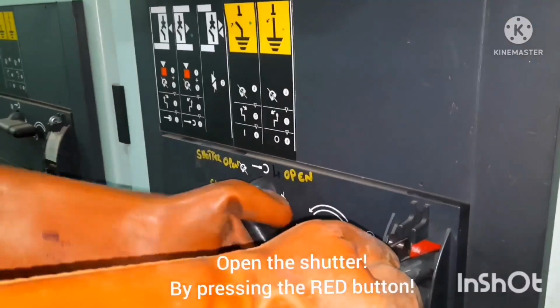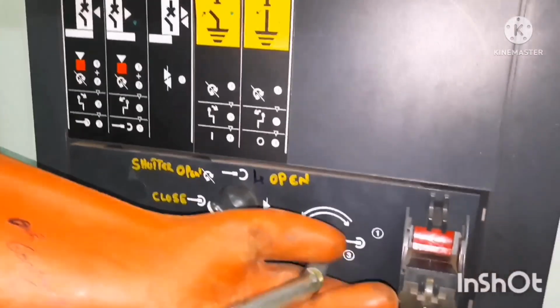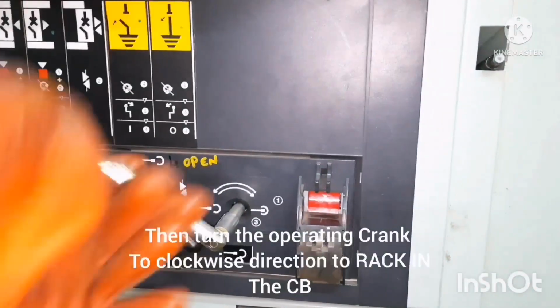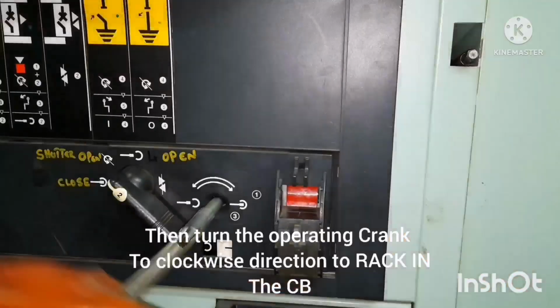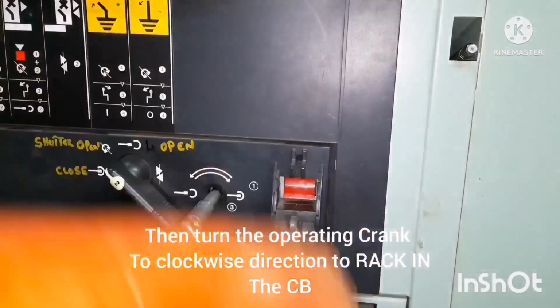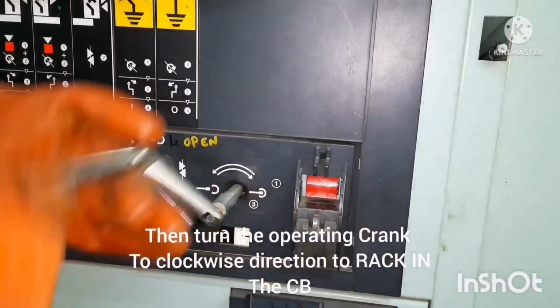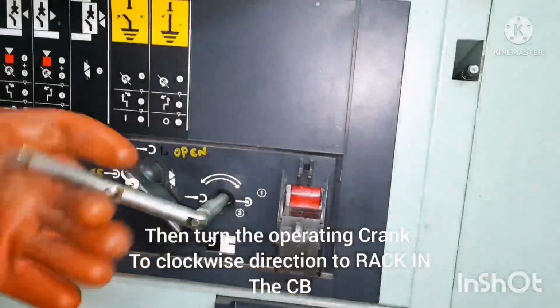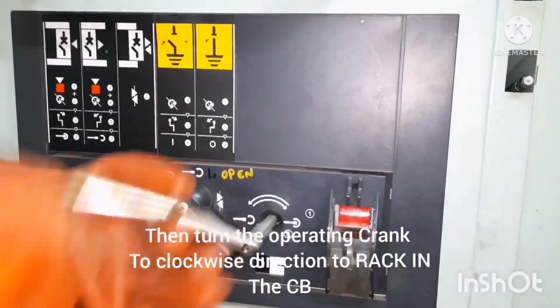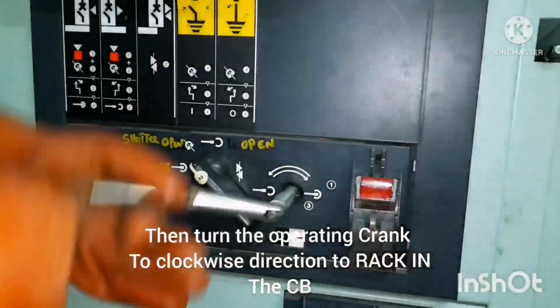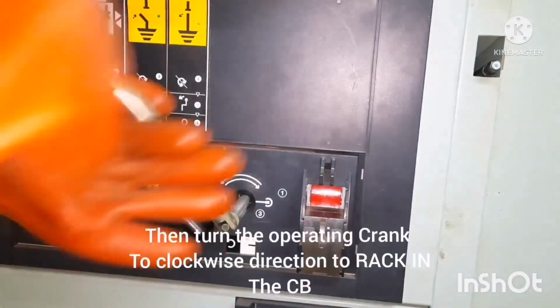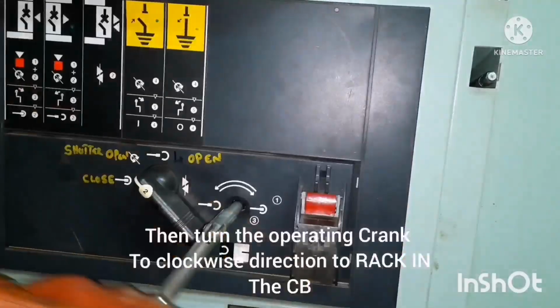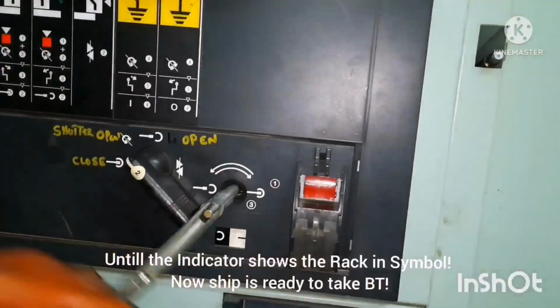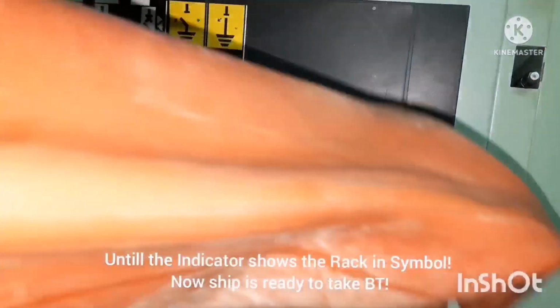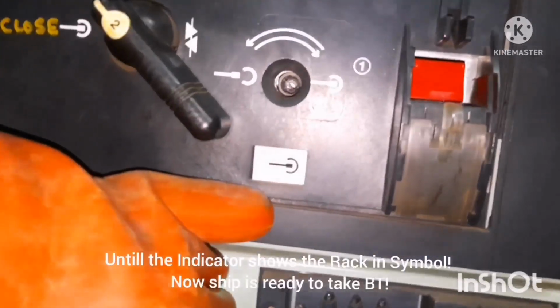Next we have to rack in. Open the shutter, press the red box, and the shutter is opened. Now you can insert the lever and crank it clockwise for racking in the circuit breaker. That is what we are doing now. Once the racking is done, you can see the position indication. Keep turning the lever clockwise till the circuit breaker is inserted, and you can see the indicator symbol. This symbol should come.